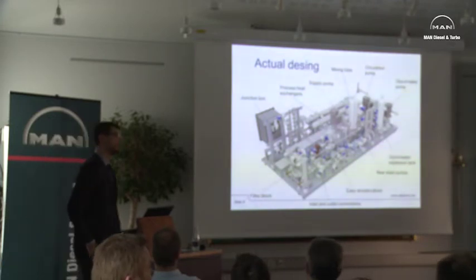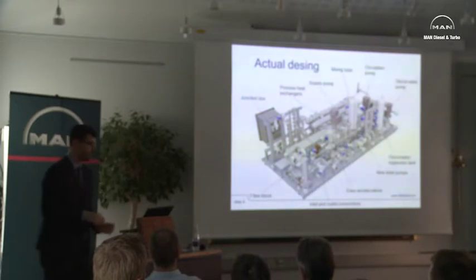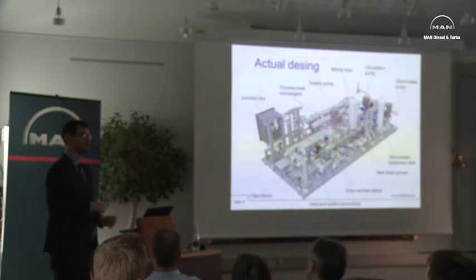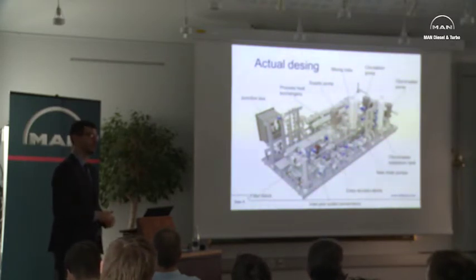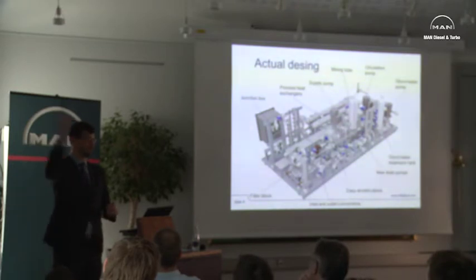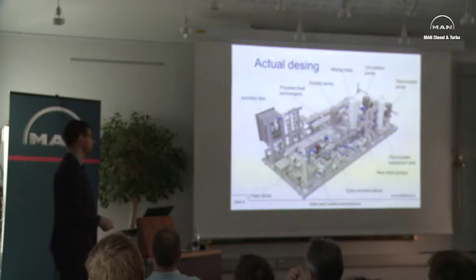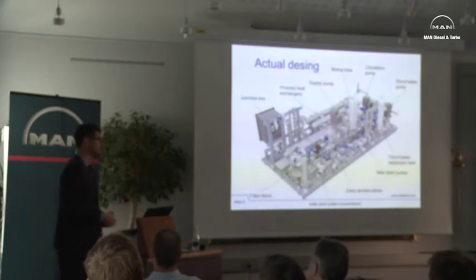Which impurities can cause problems for the engine? What we found in the baskets, you mean? Yeah, for example. I think initially there was a lot of debris from the ship manufacturing, so perlite or a lot of solids like this. I know about other issues regarding oil contamination of the methanol coming through the system, but that was not related to how dirty the methanol could be, but more to how you separate the oil that comes back from the engine into the daily tank. The tank should be properly built by the yard so that this separation comes naturally and you do not pump the oil back to the system, because then you can create emulsions, and in some filter element geometry, this emulsion could just block the filter element.